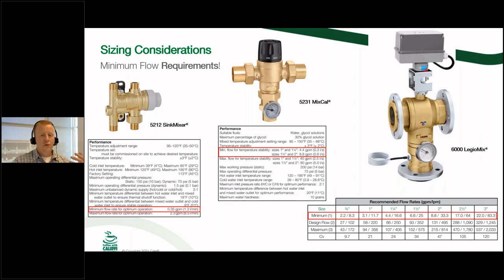But then you work into our high flow thermostatic mixing valves. This is going to be your point of distribution mixing valves. And you'll notice that the 1 inch and 1 1/4 sizes are going to have a minimum flow of 4.4, and on 1.5 inch and 2 inch, 8.8. Okay. You're not going to get that from a single lav. You're not going to get that from a couple of lavs, even a shower thrown in there, chances are. So, how do you deal with this? And even worse, you get into the Legio mix, that big 3-inch monster that's flanged and can flow enough for an entire city block. Okay, it has a minimum flow requirement of 22 gallons per minute. So again, how do you make up for this? How do you do that?